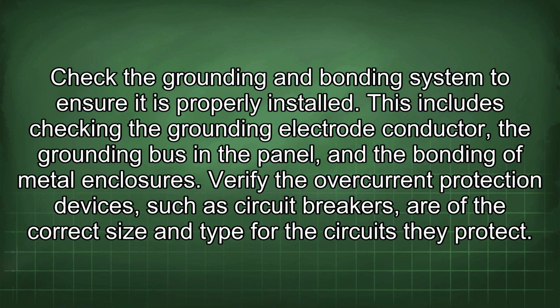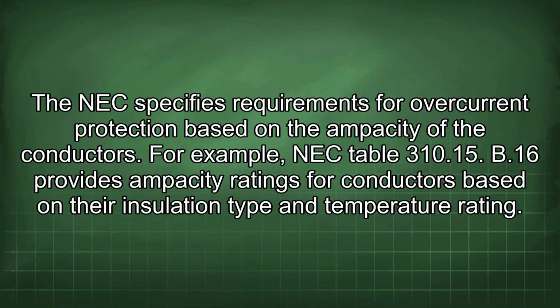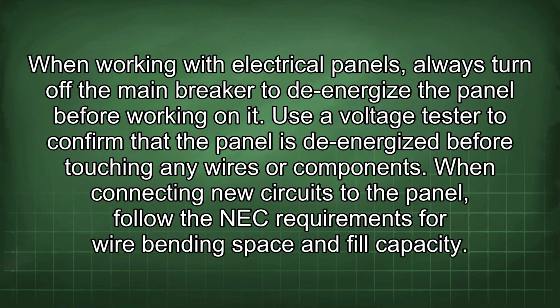Verify the overcurrent protection devices, such as circuit breakers, are of the correct size and type for the circuits they protect. The NEC specifies requirements for overcurrent protection based on the ampacity of the conductors. For example, NEC Table 310.15(B)(16) provides ampacity ratings for conductors based on their insulation type and temperature rating. When working with electrical panels, always turn off the main breaker to de-energize the panel before working on it. Use the voltage tester to confirm that the panel is de-energized before touching any wires or components.